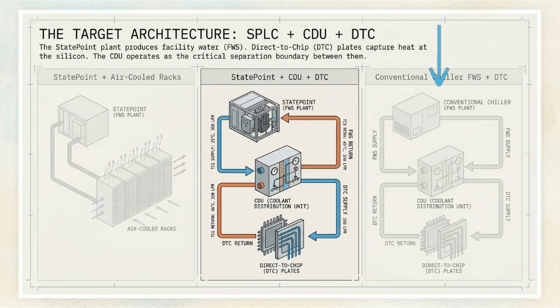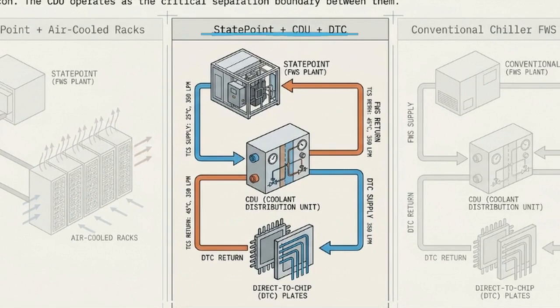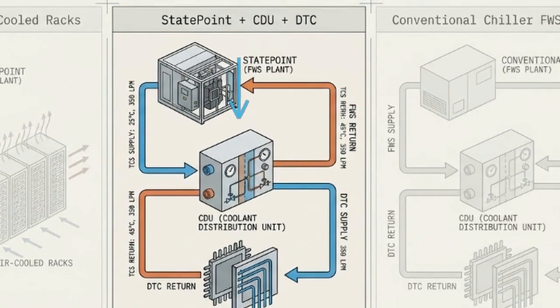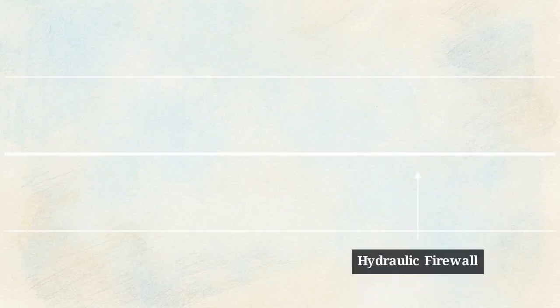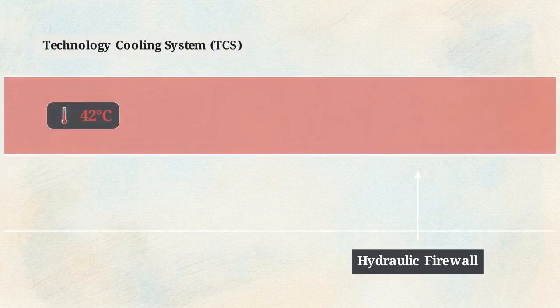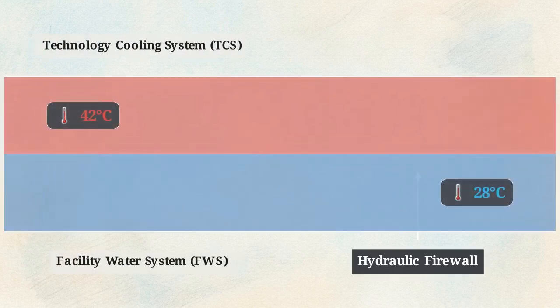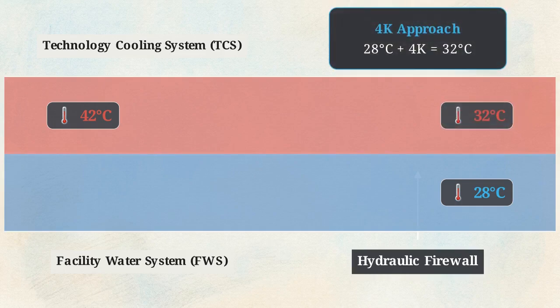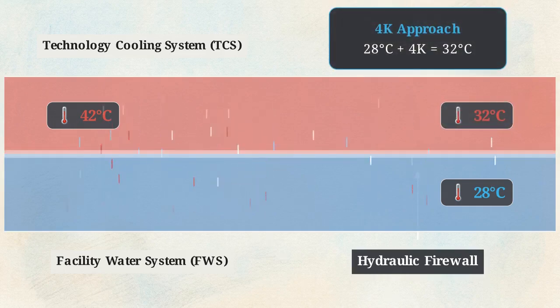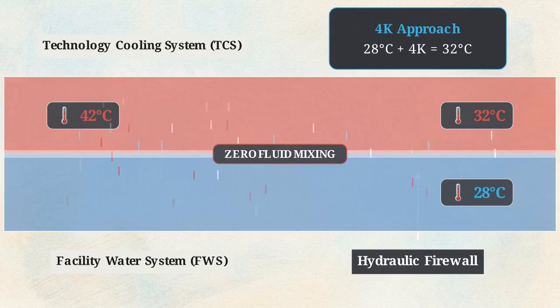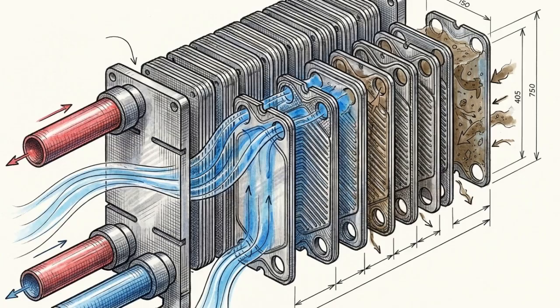Looking at these architectures, the right shows a conventional chiller. The middle illustrates our target: a StatePoint plant, coolant distribution unit, and direct-to-chip plates. The CDU acts as a hydraulic firewall, segregating high-pressure exterior water from the microfiltered technology cooling system. Within this boundary, 42 degrees Celsius return fluid from the servers meets 28 degrees Celsius facility water supply. This achieves a highly efficient 4 Kelvin approach temperature, transferring massive amounts of heat without a single drop of fluid ever mixing. This transfer occurs across plate heat exchangers.